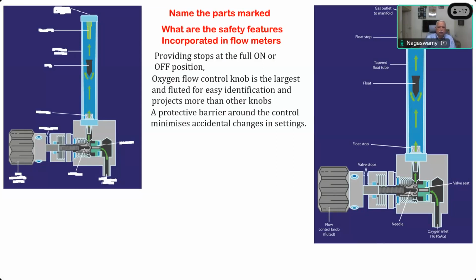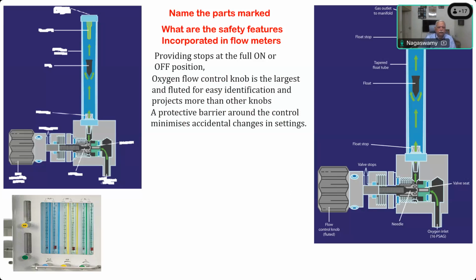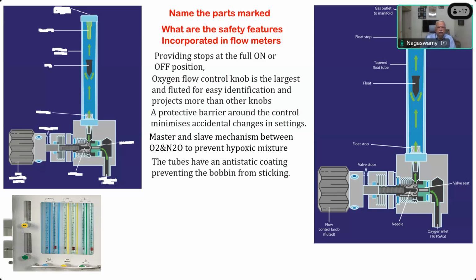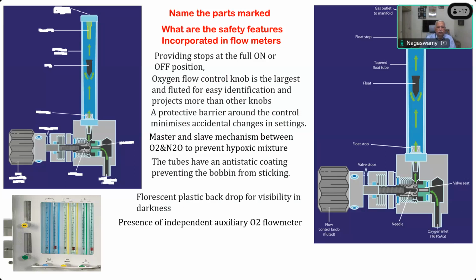Protective barrier around the control minimizes accidental changes in the settings. This is the protective barrier. You can see that this is a rod-like thing so that your hand does not touch the knob unnecessarily. So this is an effective barrier. And master and slave mechanism between oxygen and nitrous oxide to prevent hypoxic mixture. And the tubes have anti-static coating preventing bobbin from sticking, and fluorescent plastic backdrop for visibility in darkness.